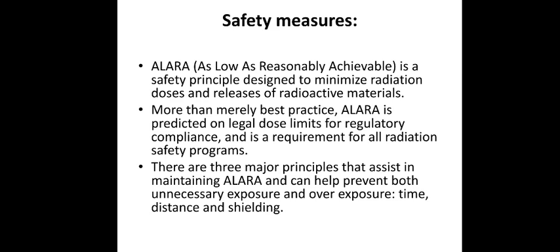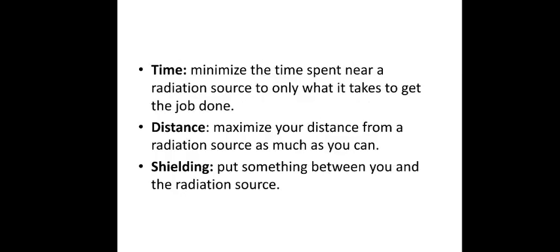There are three principles in ALARA: time, distance, and shielding. Time: minimize the time spent near a radiation source. You need only a few minutes, and after that if you can come out of it, then it is well and good. You don't have to unnecessarily stand in front of a radioactive element for a longer time. Minimum time of exposure is important.